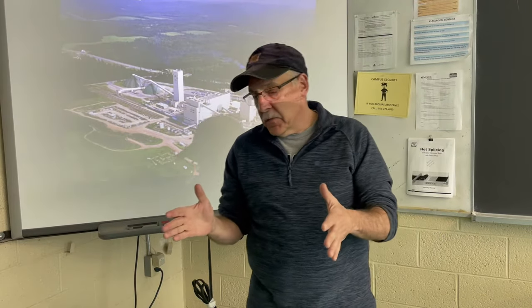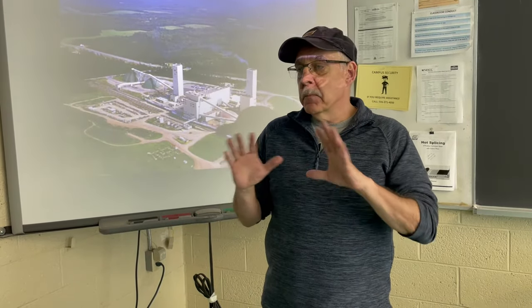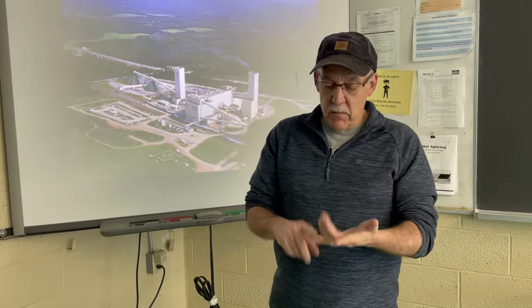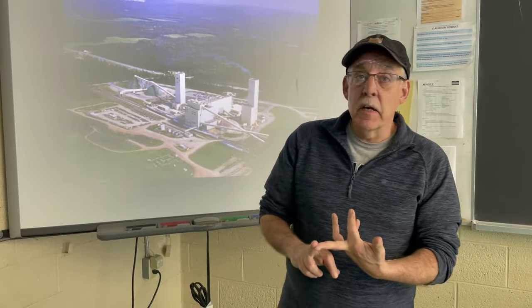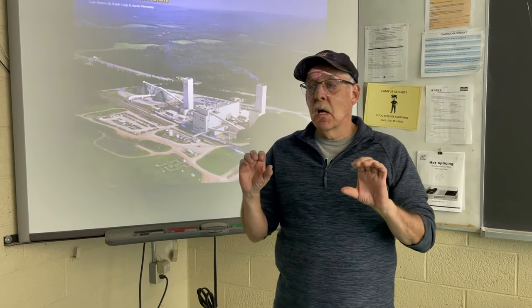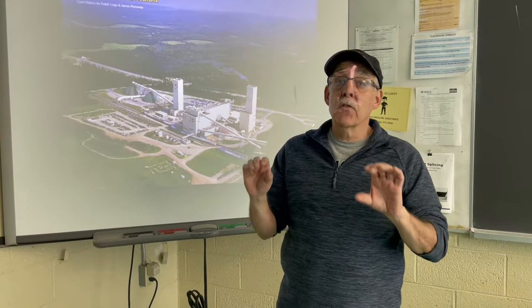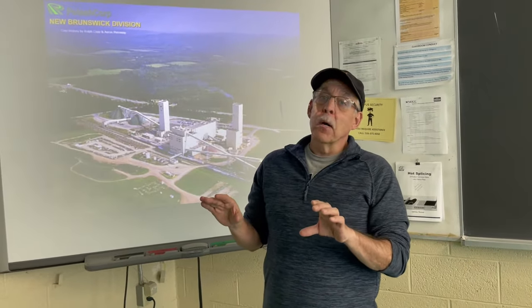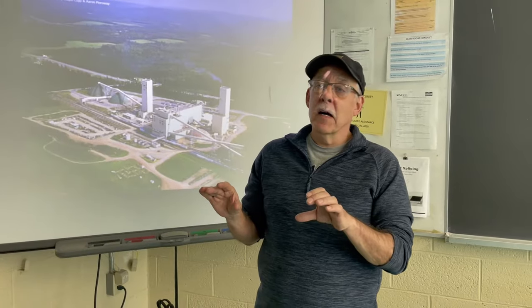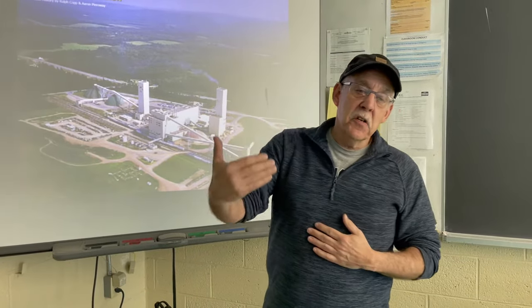So we put that piece of equipment in, we let it warm up, get it running, and then we take a vibration reading, we take an oil sample, and we take a temperature reading, and we use those as a baseline. Then we look for change from the baseline. No change from the baseline, no problem. Change from the baseline, we could have a problem, may or may not. Now we have to investigate further.